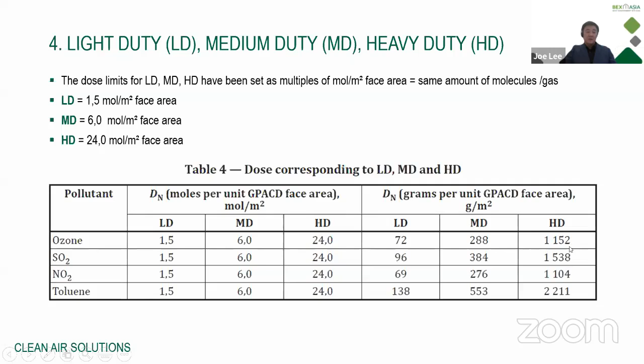And if you look at the table, this part on the left-hand side refers to mole per unit. So 1.5 mole for all the gases, but if you look at the grams per unit, it's very different for different kinds of gases. Different gases have different weights, even though the mole per meter square is the same. So when we challenge the filters, we put the LD, meaning we put 1.5 mole. The next slide will cover that in more detail. For the time being, just take note, LD refers to 72 gram, which is 1.5 mole for ozone, MD is 6 mole, which is 288 gram. And last but not least, HD is 24 mole, which is 1,152 gram of ozone.